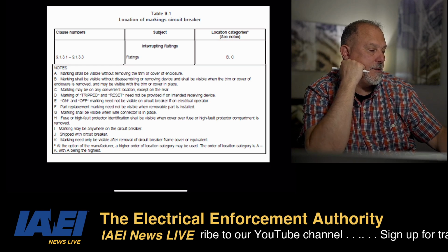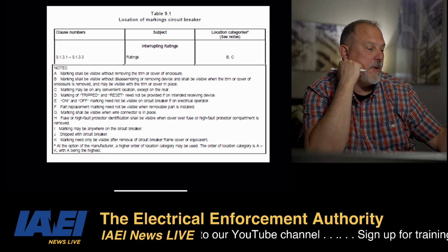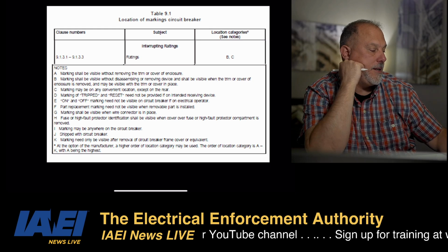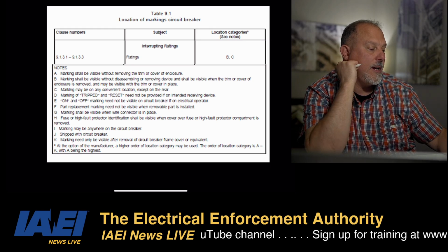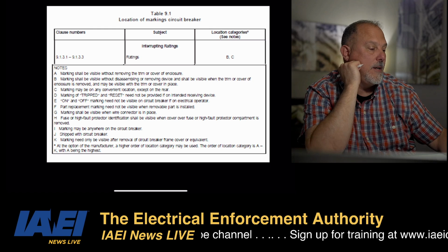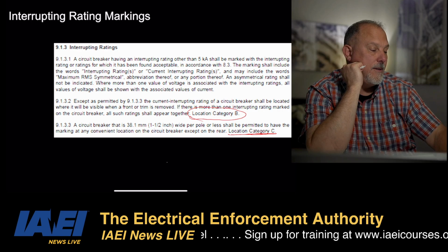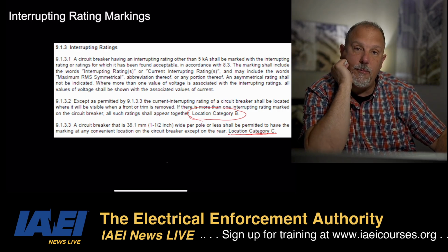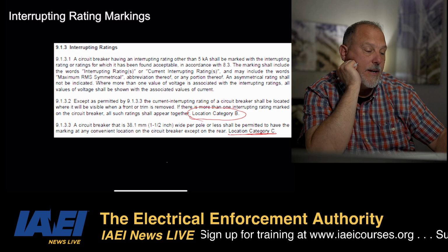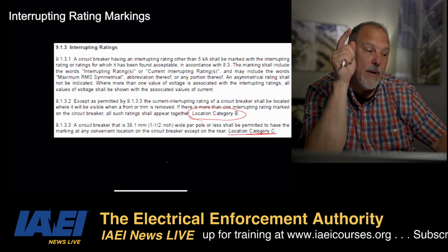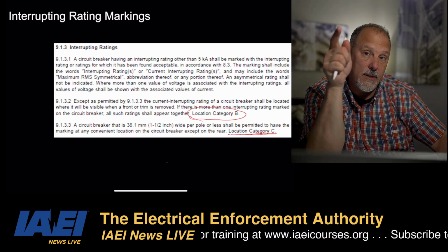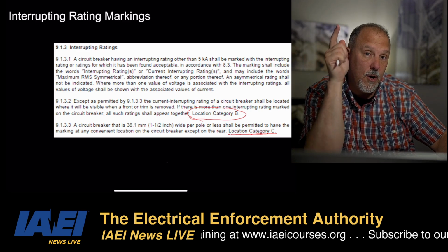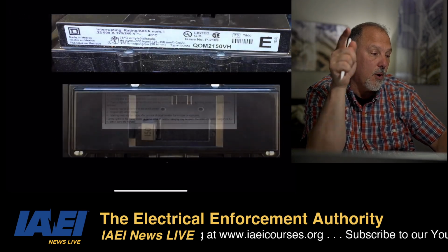Interrupting ratings, B and C. B: marking shall be visible without disassembly. And C: marking may be on any convenient location except the rear. And that will be dependent upon, again, 9132 or 9133. So my answer to that question would be it depends on where, but you're always going to have an interrupting rating marked on the device.